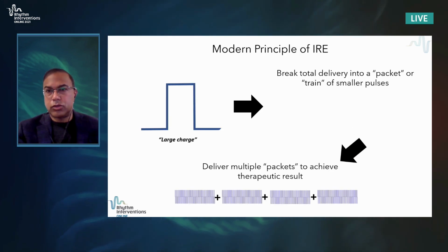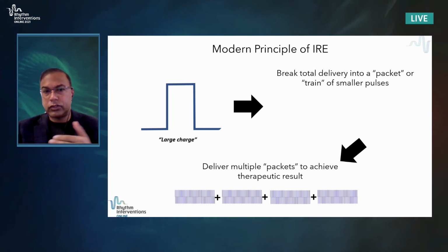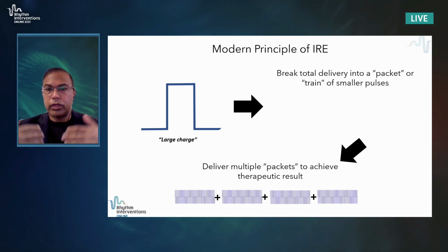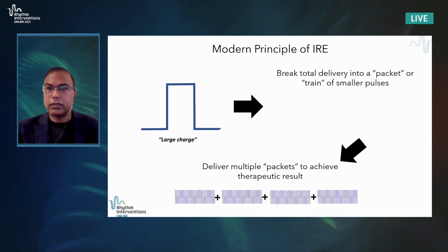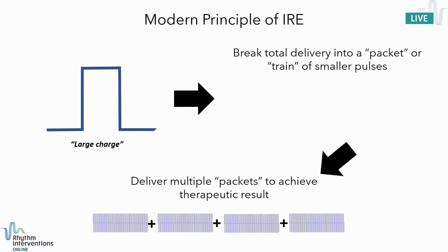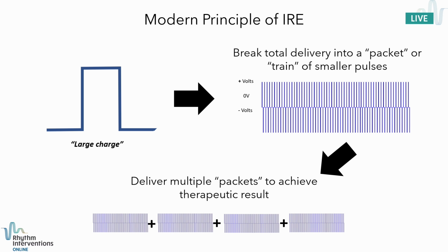The modern principle of irreversible electroporation is basically, and why we now have it today and we didn't have it 20 years ago, is because 20 years ago we had defibrillators which could deliver a very large charge. But with progress in technology, we can break this large charge into a series of much smaller pulses which can be delivered in packets or trains, which give you the cumulative effect of the large charge, but doesn't cause the patient to jump off the table or the other thermal damage that may be associated with a large charge.